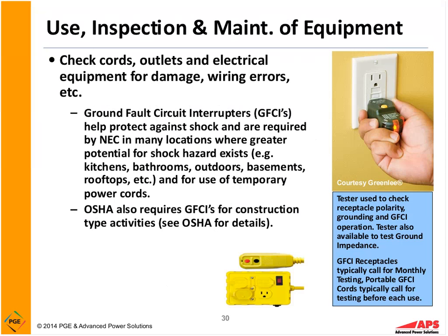It's very important that we inspect our equipment. So we need to properly inspect our equipment, check cords, outlets, and electrical equipment for damage and wiring errors. So if we have GFCIs, as you can see in the picture in the upper right-hand corner there, and also at the bottom of the slide here, we have a GFCI that would be used, let's say, for a construction site or a site where we may be doing electrical maintenance. If we look at these, right on the GFCI there, it says test before each use. Right on the button, it says test before each use.